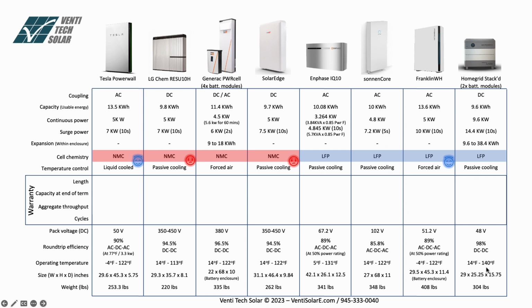And again, here in the HomeGrid stack, they're pushing the limit of what the LFP can do. At 140 degrees, 14 degrees Fahrenheit, this is a stretch. So this will probably shorten the life of the cell. I would not recommend it, especially for passive cooling, but there may be something that they're doing. Maybe there's some electronics that will disconnect the battery in extreme cases. I don't know, but this to me seems a stretch.